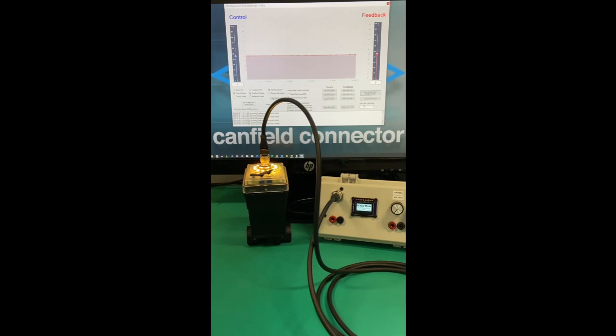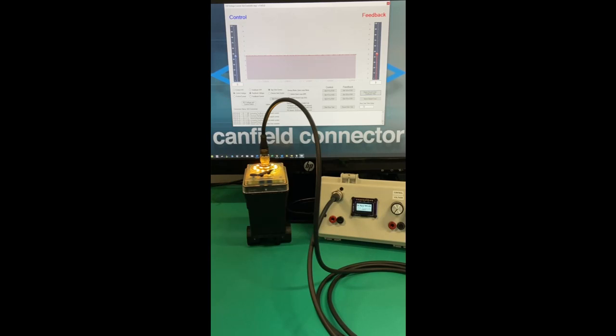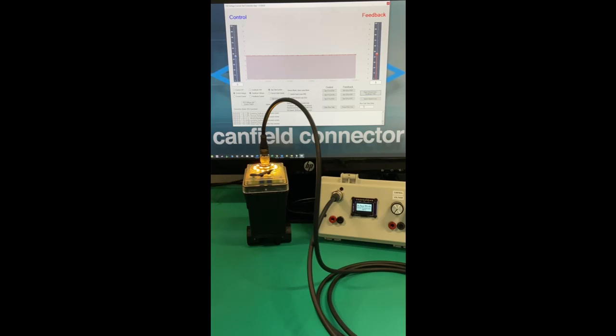When pressing the demo closed-loop feedback only button, the VCC initially provides an open loop control signal to place the valve at a position equivalent to a control voltage value of 5 volts, which is approximately halfway open for the stroke position. This gives the stepper a mid starting point when showcasing the operation of closed-loop mode. The feedback voltage is set to a value of 5 volts at this time as well.